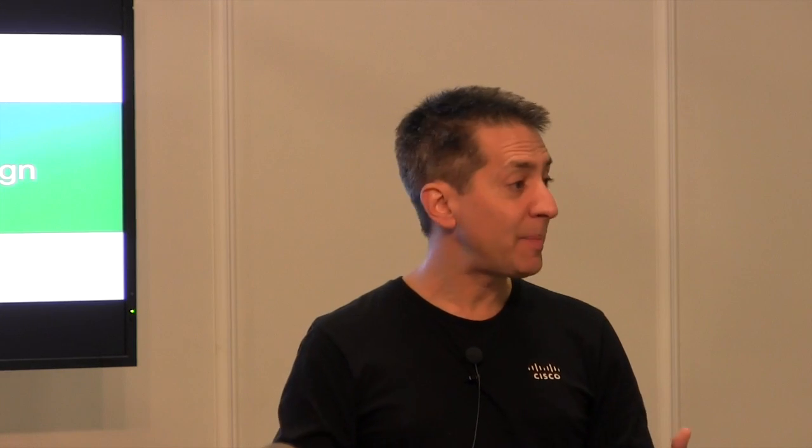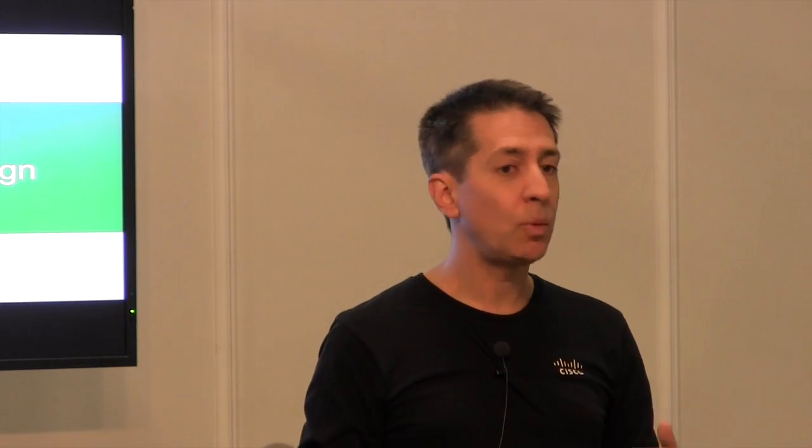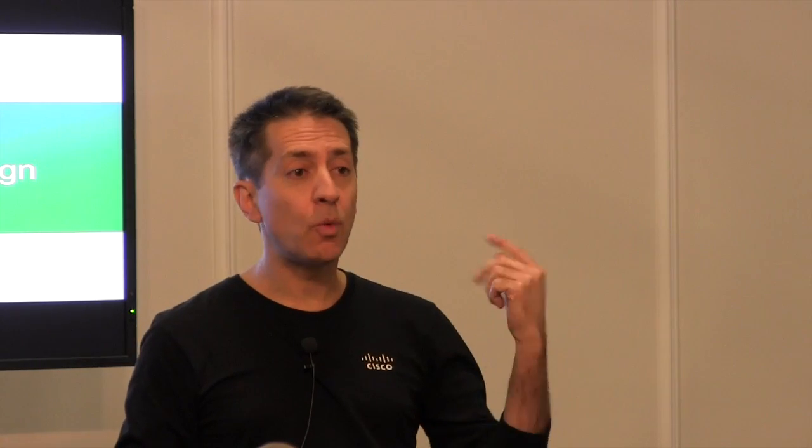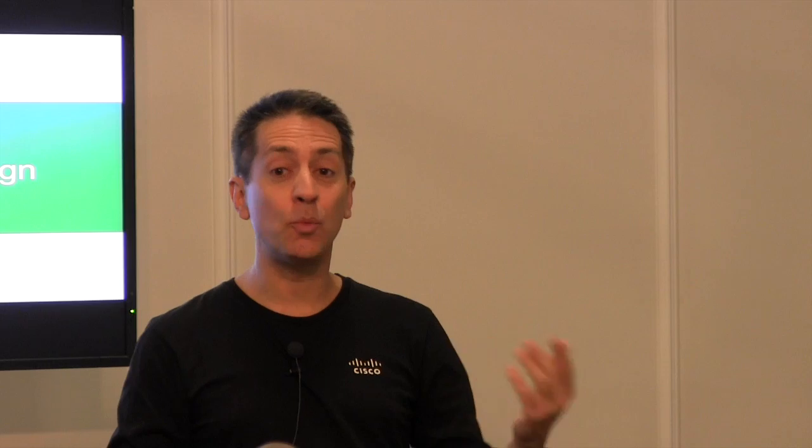The protocols were one thing we started looking at. The next thing we saw is that once we are providing power, we're going to need features that enable that power to be resilient. So what we have is perpetual PoE. If the switch reboots, we don't want all the lights to go out. Perpetual PoE will keep the PoE up — if the switch software reboots, you don't lose any power to the lights. You'll get a flicker within sub-second, undetectable.